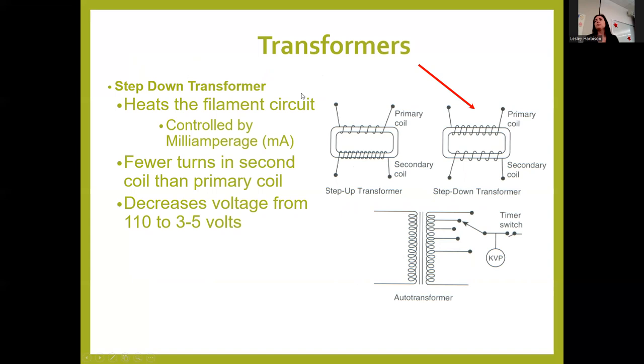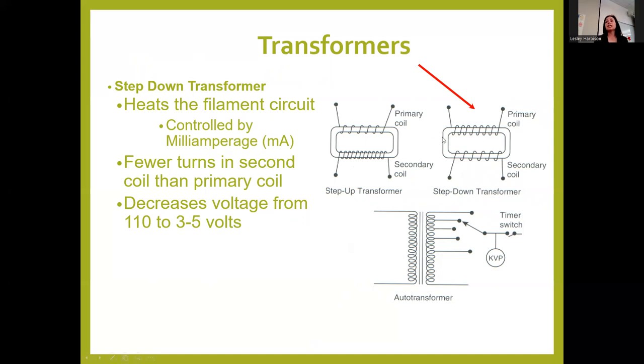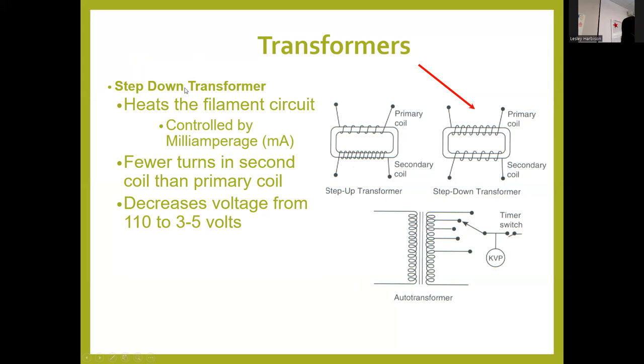Looking at the step-down transformer diagram: it heats the tungsten filament, it heats up and makes an electron cloud, and it's controlled by MA. There are fewer turns in the secondary coil than the primary, and that's part of why voltage goes down — decreasing from 110 to three to five volts. The step-down transformer is on the cathode side, where your tungsten filament is, and your electricity runs through this transformer before it gets to the filament.